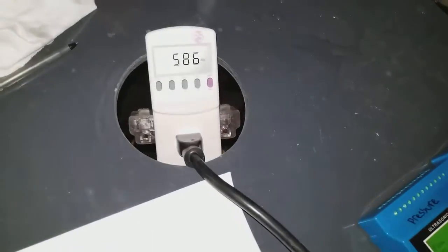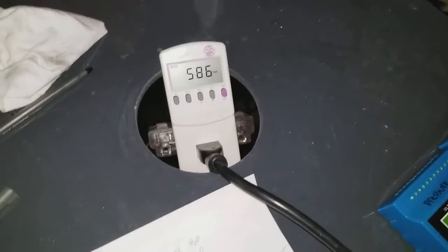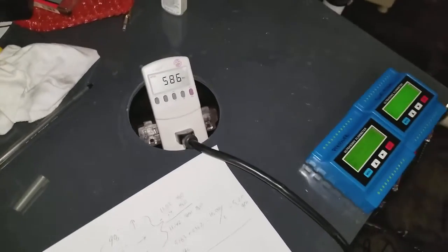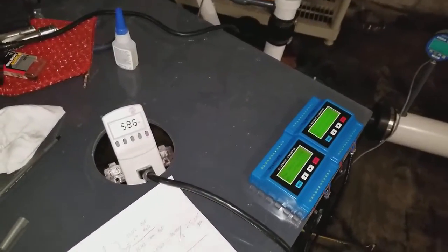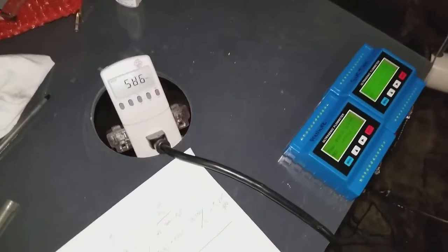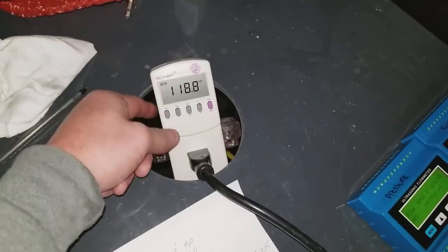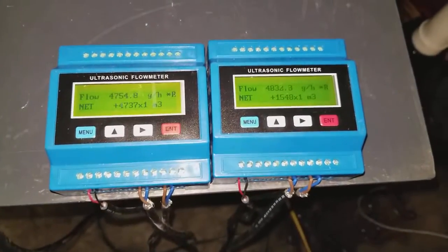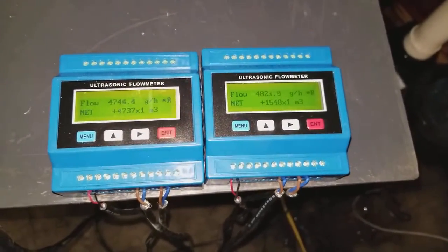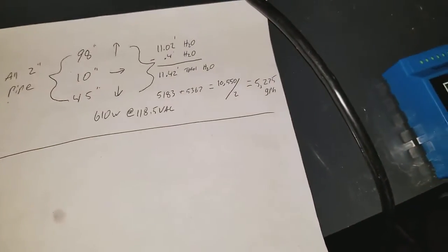Another way of showing that: we are doing 586 watts of work right now. With centrifugal water pumps, the higher the pump pushes the water, the less wattage it actually uses because the impeller starts slipping. Now we're at 585 watts at still 118 volts. Looking at our flow meters, we're down to 4,825 and 4,745 gallons per hour, compared to our previous 5,275.